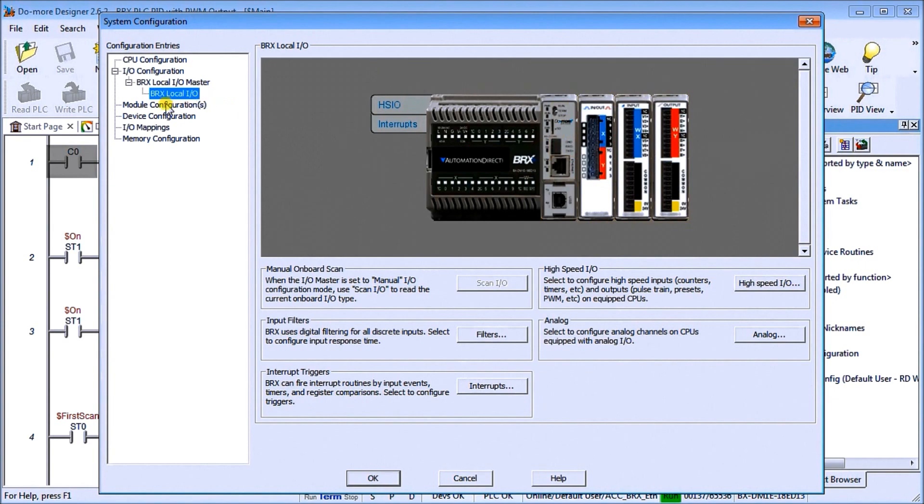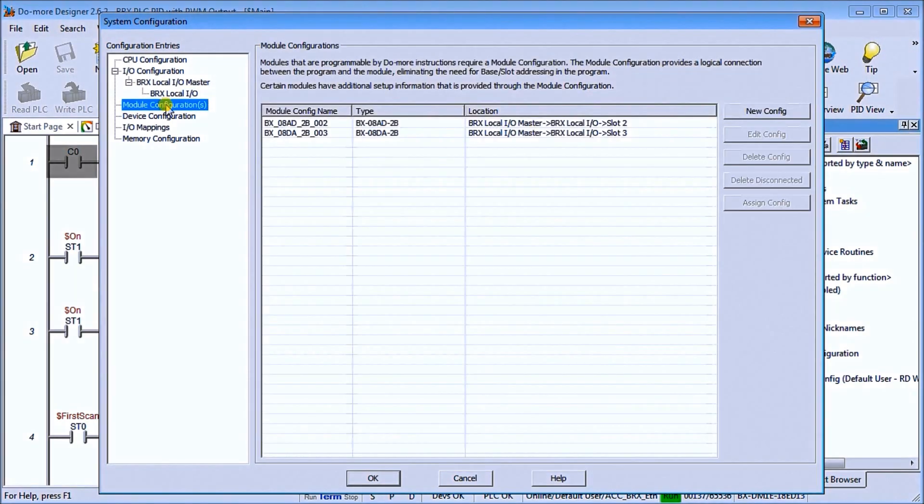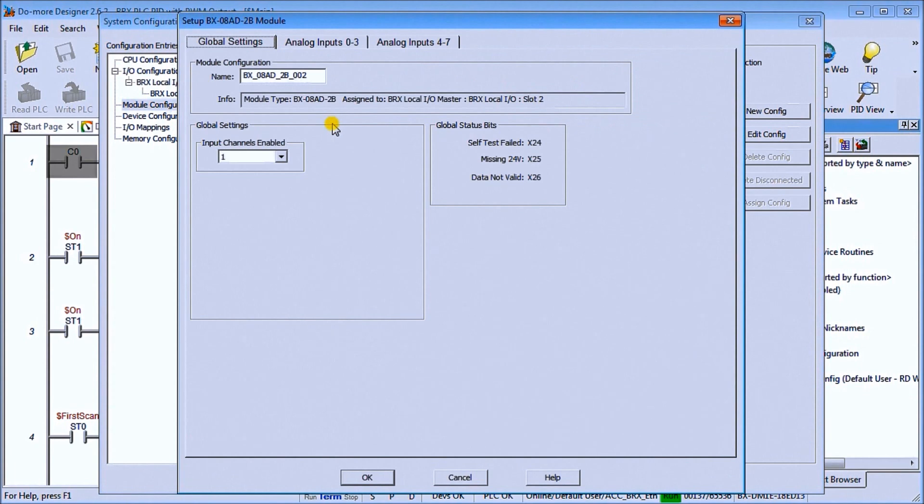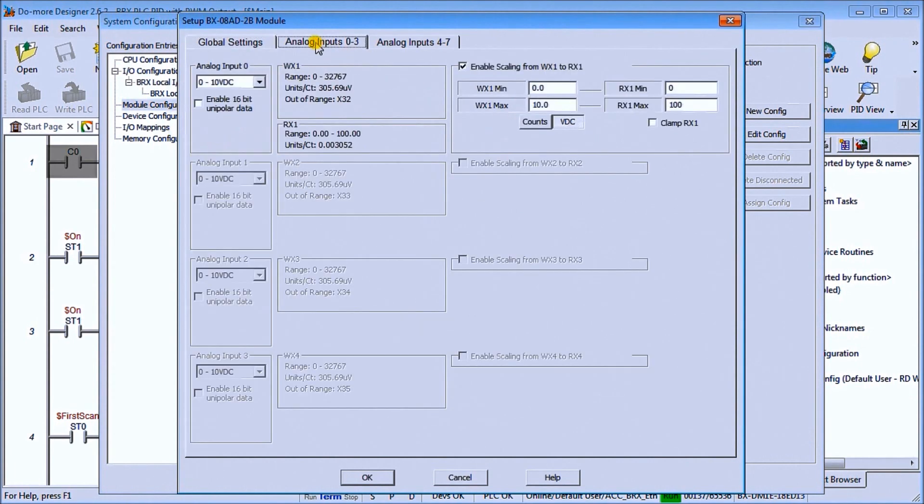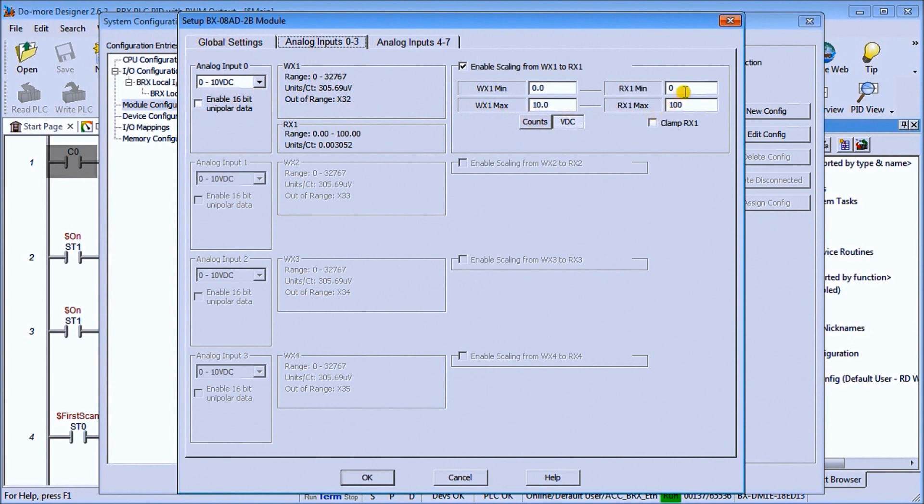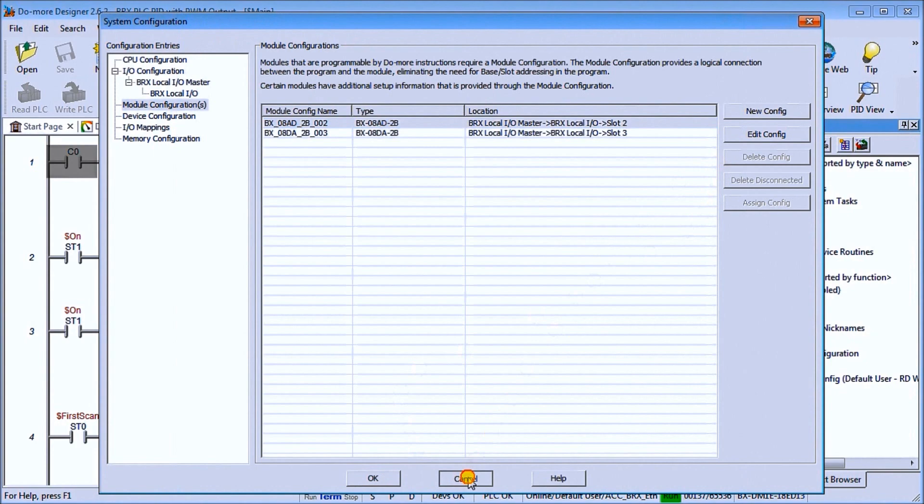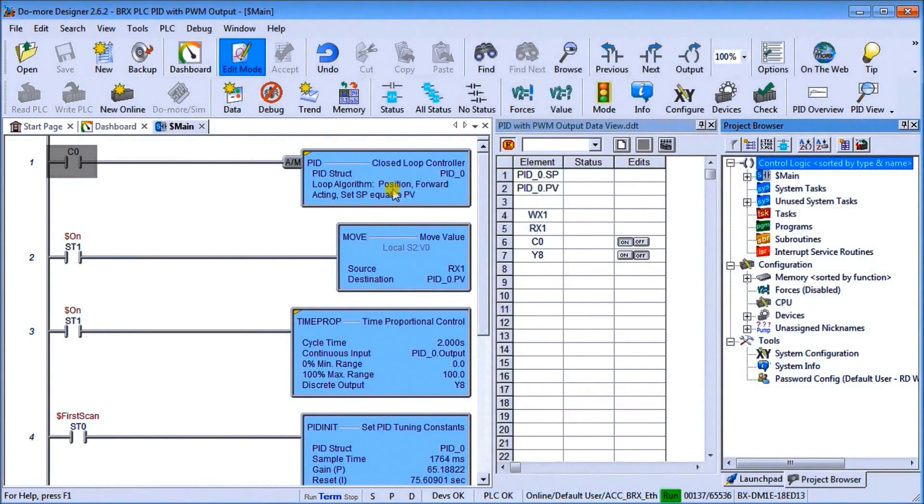We'll look at the module configuration, the analog in. We're using one channel and that channel is getting a 0 to 10 volt input and we're scaling that to 0 to 100. This will represent degrees Celsius. So that is our system hardware.